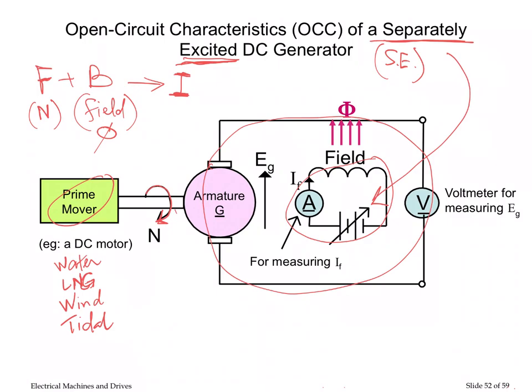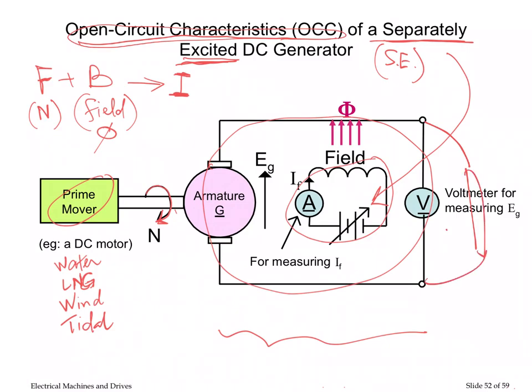We are going to express this model into a circuit and plot the open circuit characteristic — the OCC. This means we don't connect any load. The load would normally be here — whether a bulb, fan, or motor. Right now we are just measuring open circuit: we want to measure how much voltage the generator outputs when you change the speed or change the field current.